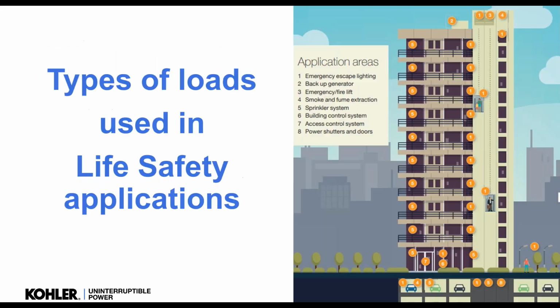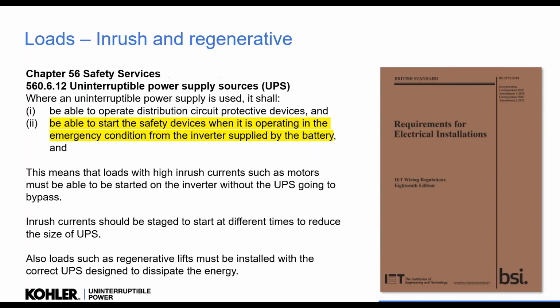Okay, so the types of load we look at in life safety are very different to a normal application for a UPS. We have to be able to start those safety devices on battery when required. So what are we going to do? We have high inrush currents, so what we might want to do is make sure the inverter can start them, but stagger the loads coming in, time them to come in, not all at the same time. That will reduce the size of the UPS.